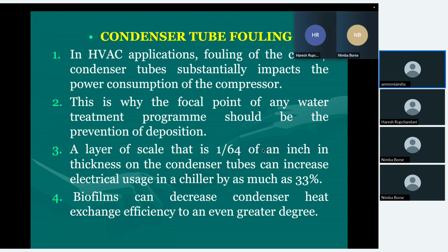When we opened that PHE condenser, it was totally coated with mud. You couldn't even see the corrugation, even the slots on the plates, and it was like a flat plate. It had to be entirely scraped out mechanically to make that condenser work again. But the client became wiser and he changed the condenser to a shell and tube condenser. The other alternative is, if you are using PHE, use RO water. It is always essential to use a water treatment plant.